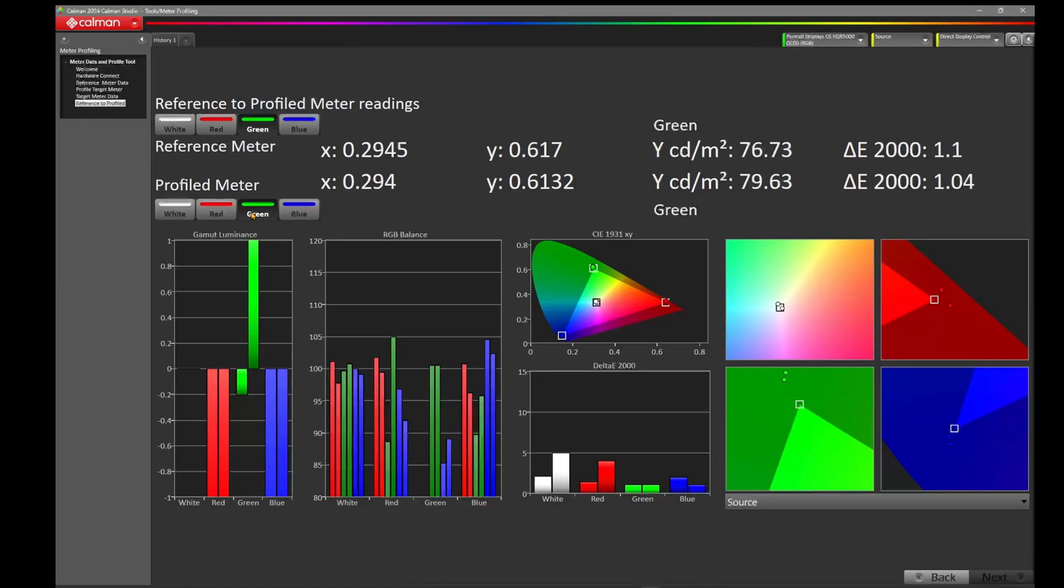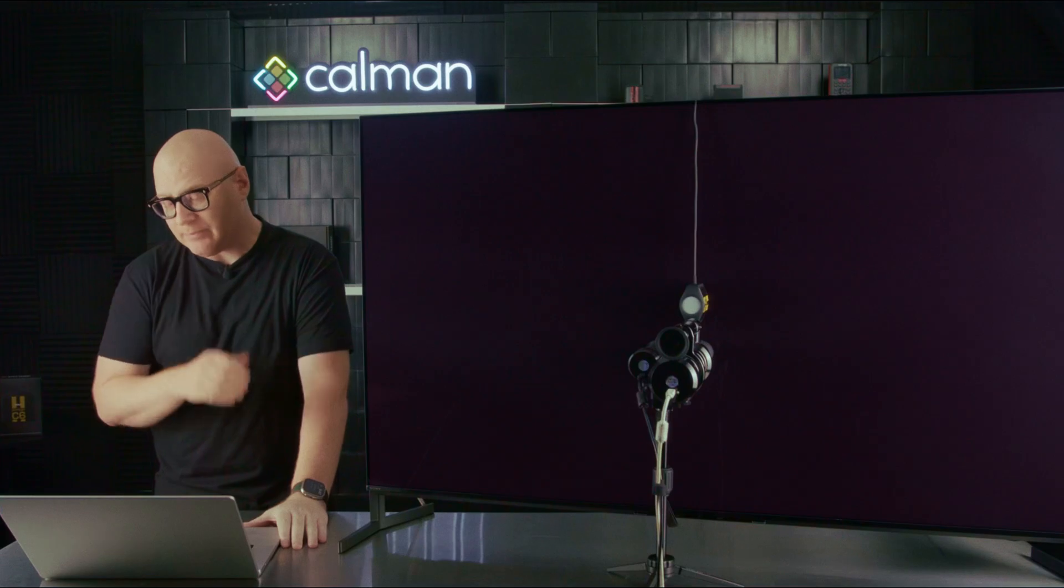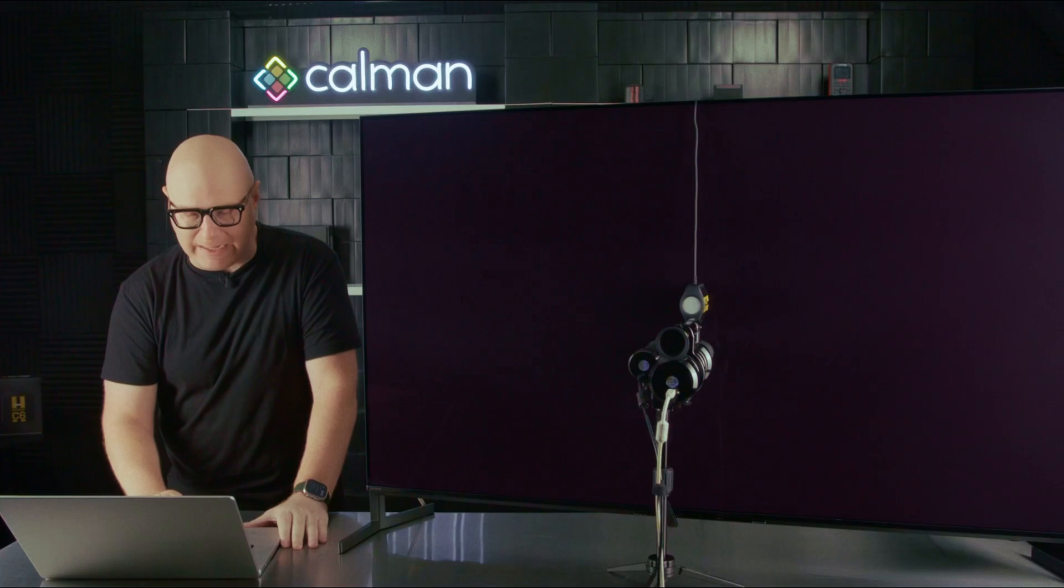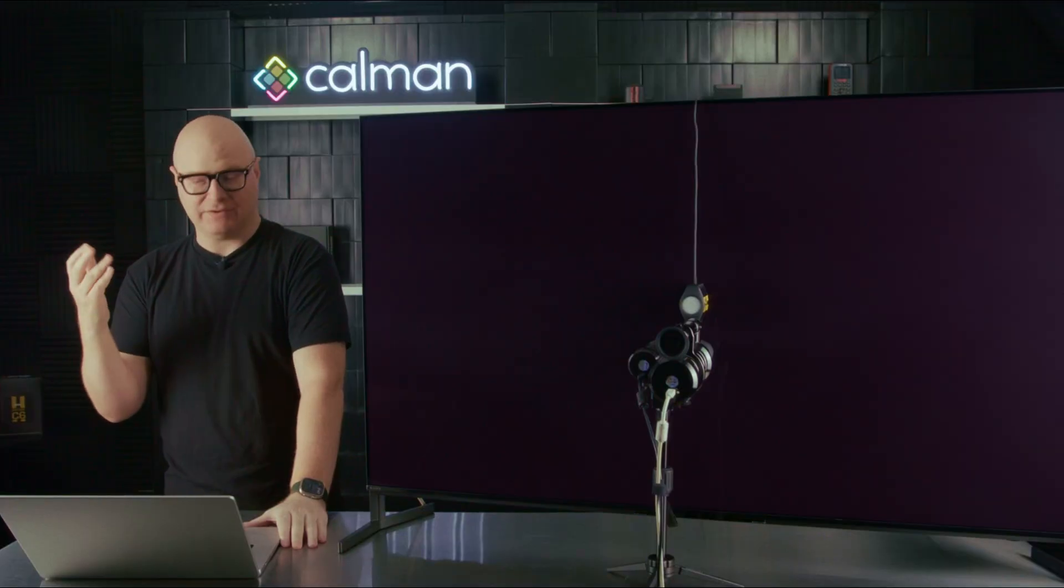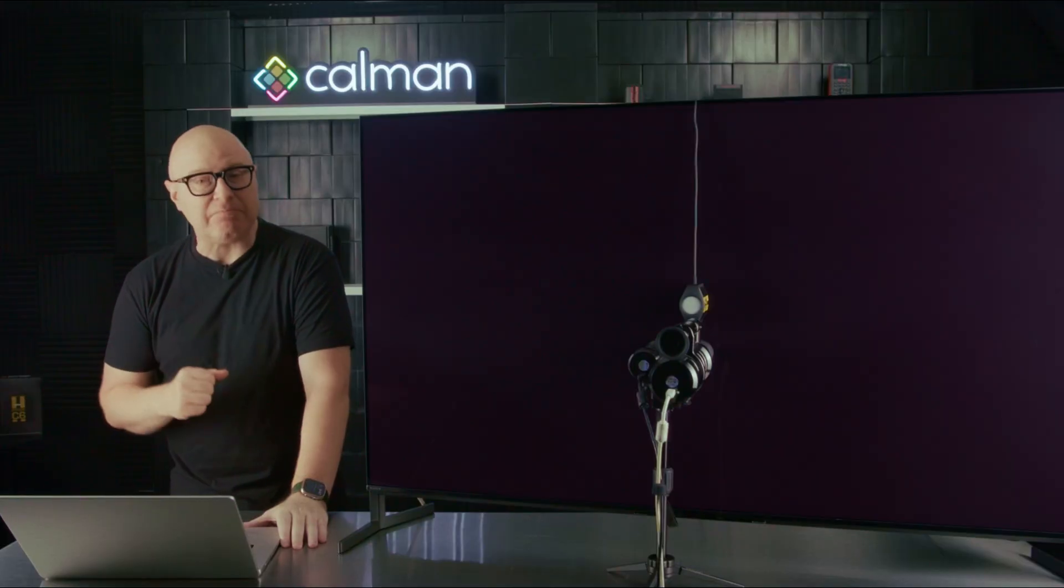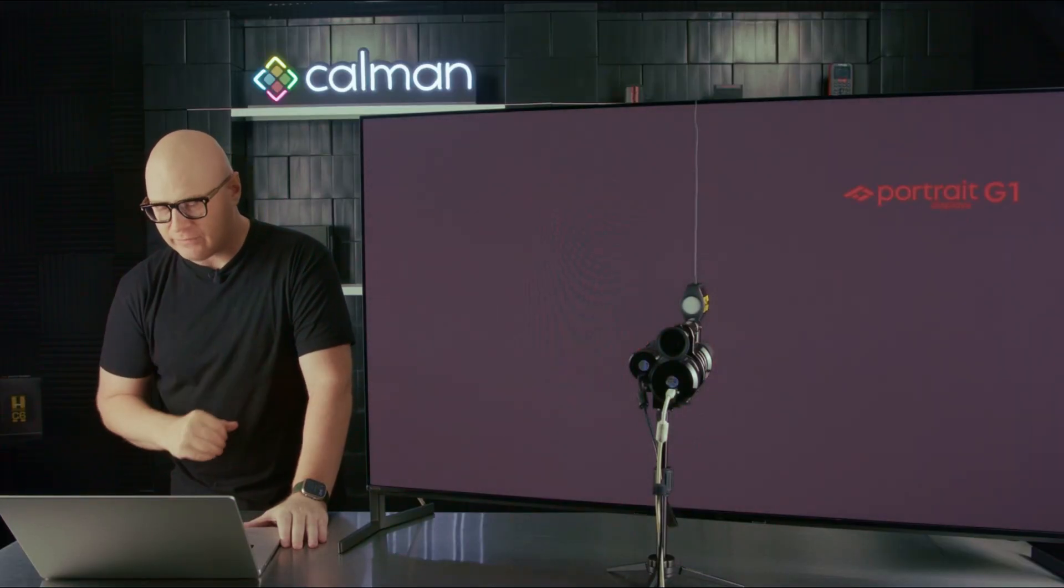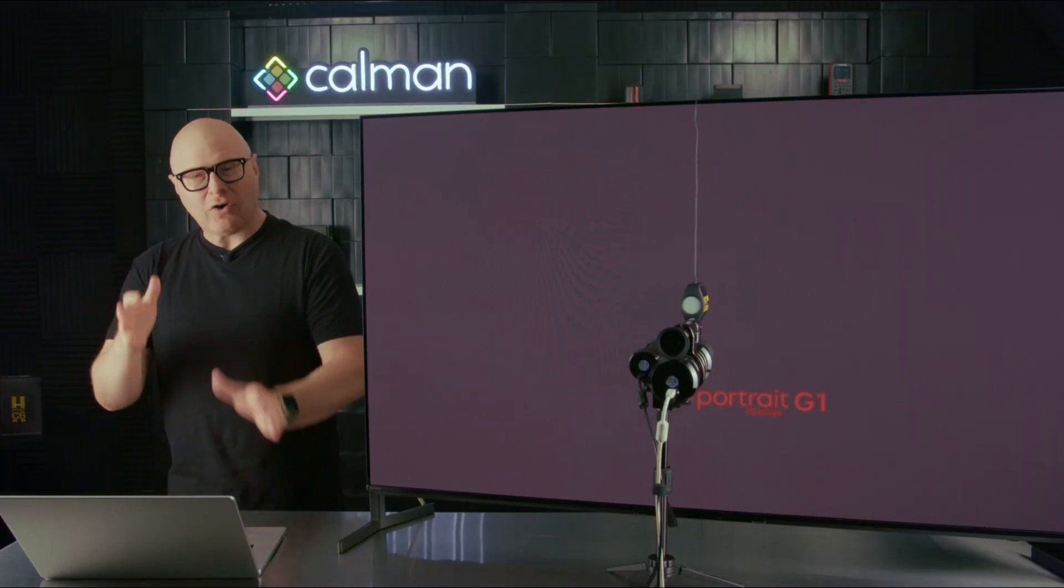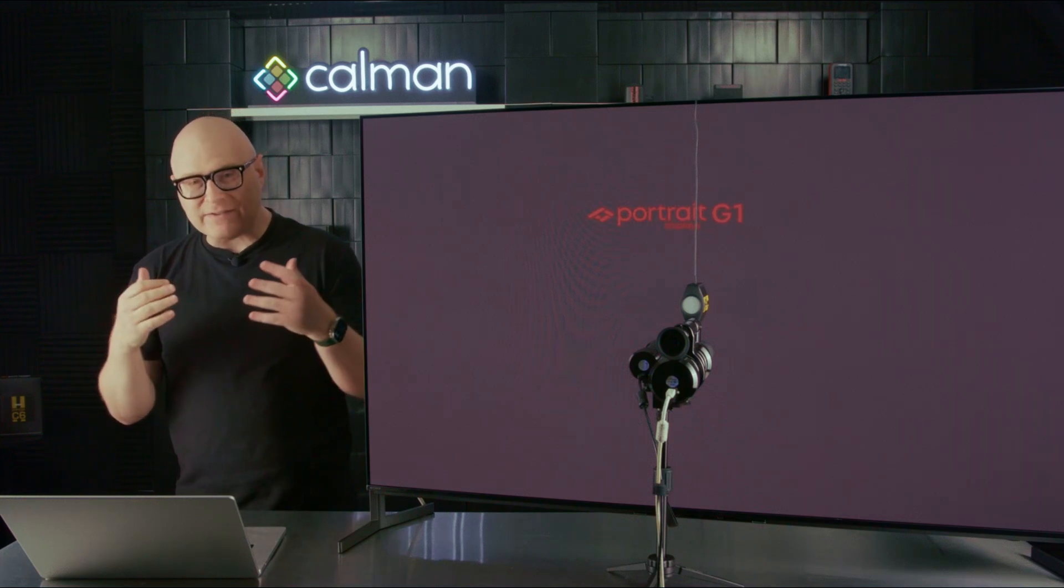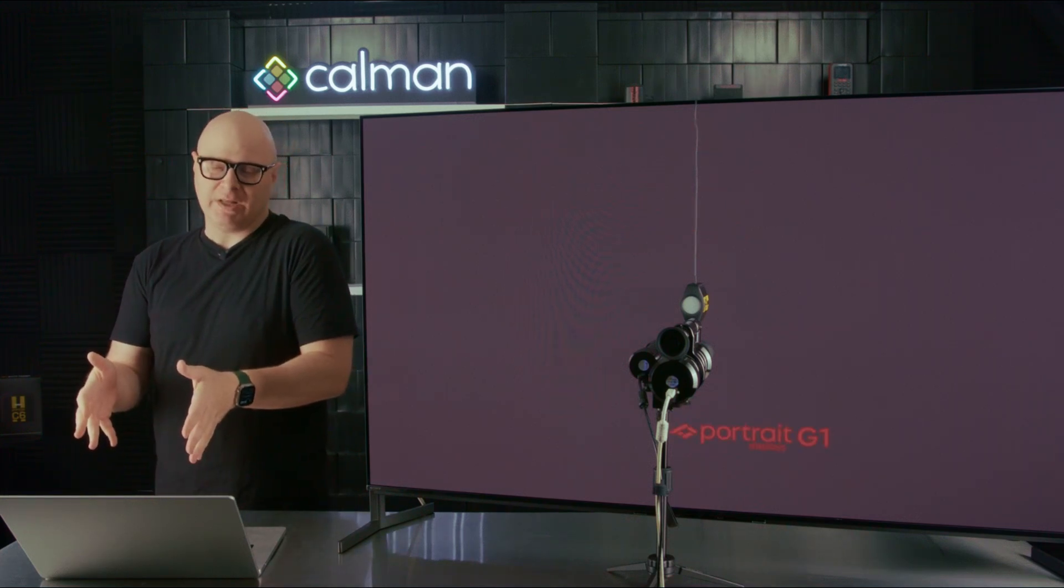Let's take another quick look at the green. 0.2945 and 0.294. Not bad. 0.617 and 0.6132. Not too terrible right at the border there. 76.73 and 79. A little bit much on that Y. Let's take a look at that blue. 0.1485, 0.1482. Not too bad. 0.0538, 0.0568. Pretty close. Remember we're in that 0.003. 6.9 and 7.38. Not too terrible there. So there are some areas you saw even in this profile where we had significant error and some where we didn't have so much error.